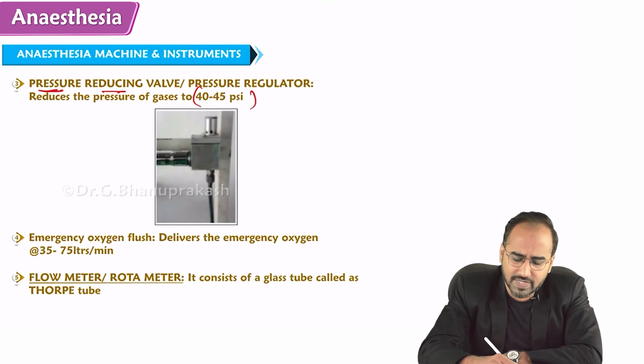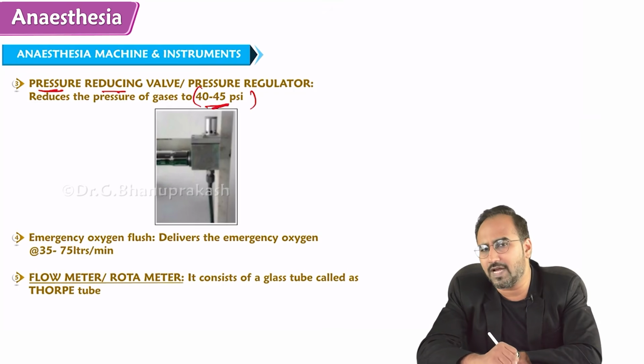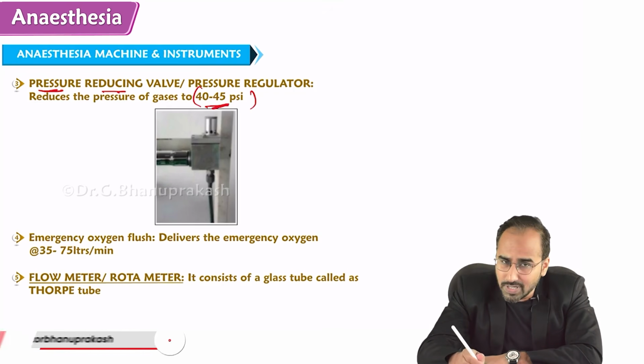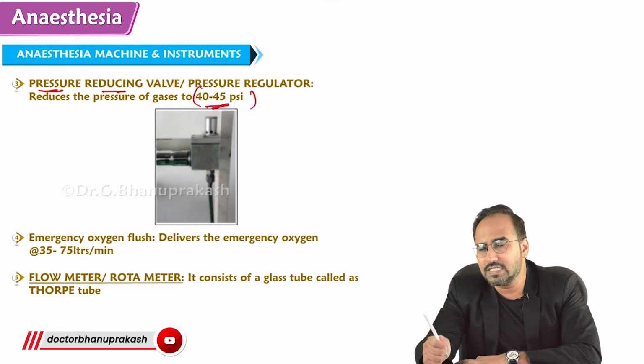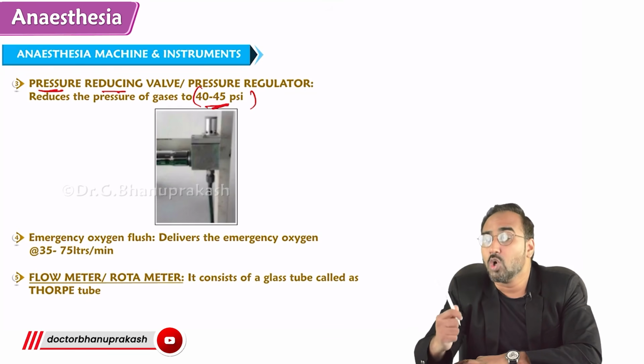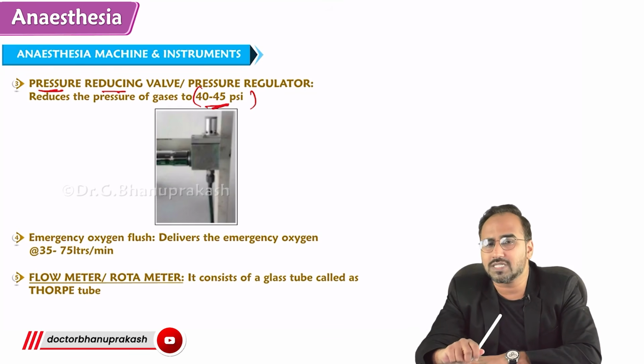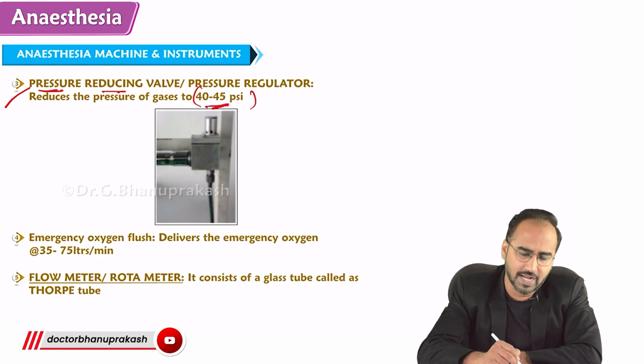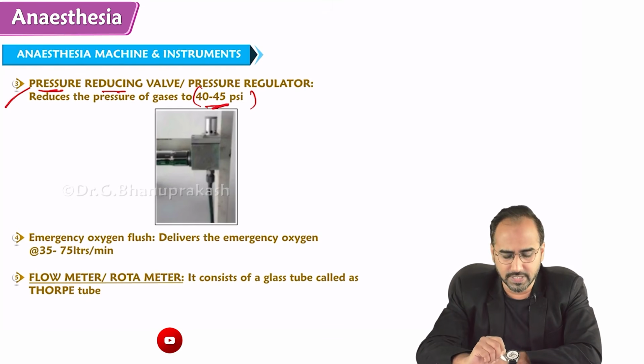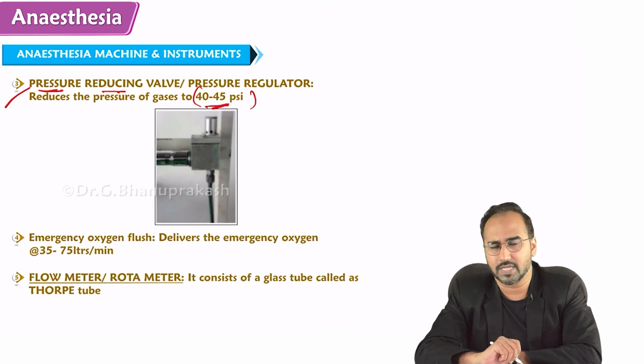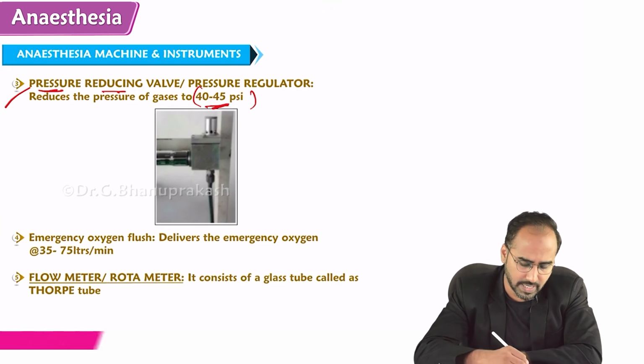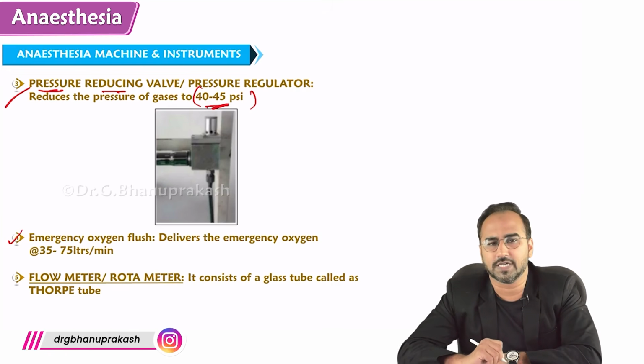Actually, this is the valve that reduces the pressure to 40 to 45 psi. I told you, the machine is used to reduce the pressure. Who inside the machine reduces the pressure? The pressure reducing valve reduces the pressure to an acceptable limit. Next, emergency oxygen flush. Guys, remember where I taught you about emergency oxygen flush?